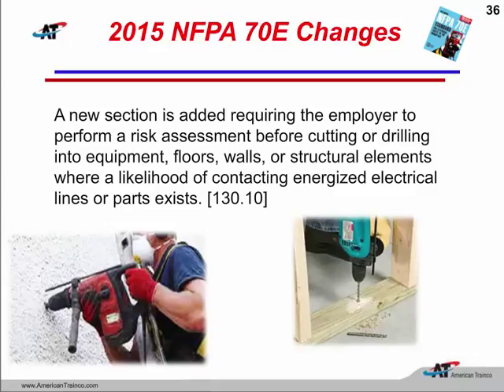We'll drill through floors, walls, especially walls, and we make no assessment there. Well, I've seen people drill through service entrance cable that's not even protected by any overcurrent device because they didn't do a risk assessment. If your facility has a thermal imaging camera, very easy, we can take an infrared scan of that wall, give us a really good idea what might be behind there. But we are going to have to do a risk assessment before we do any drilling, and that's going to be very important.